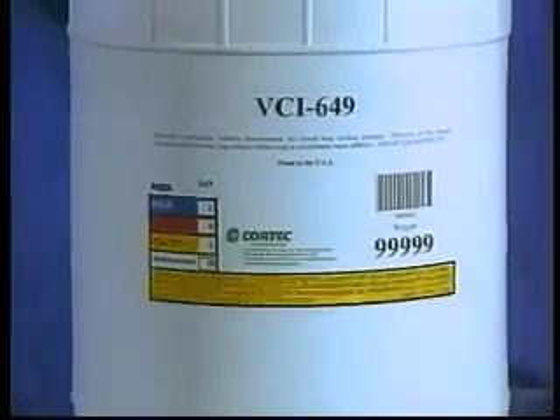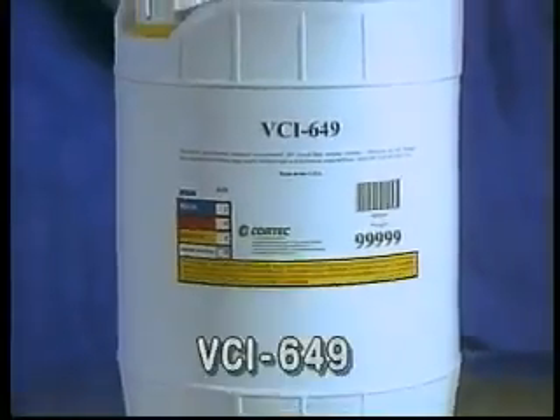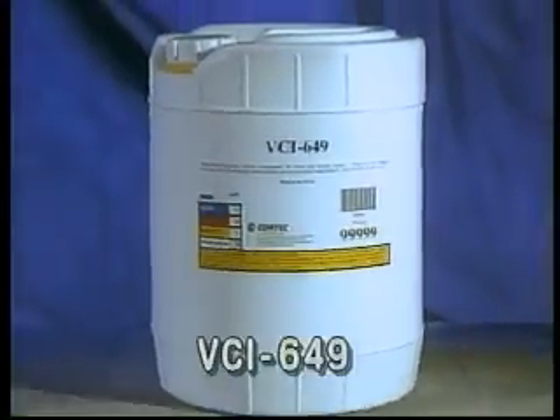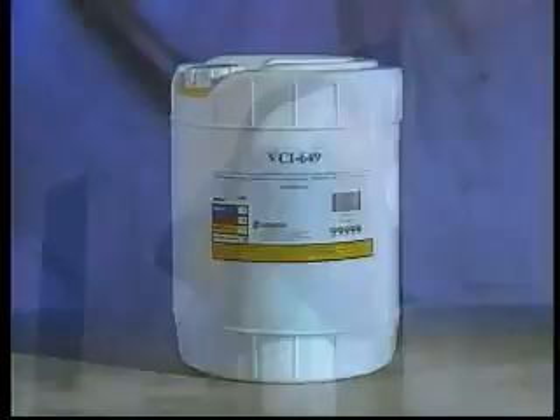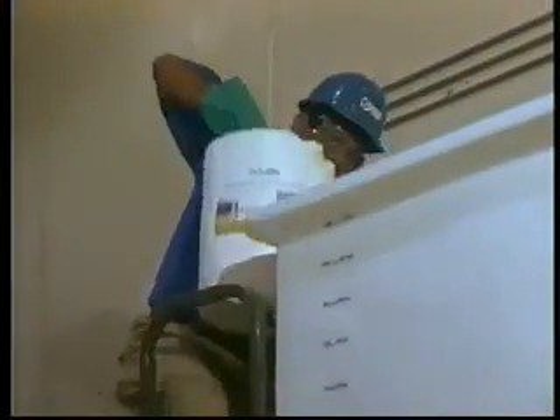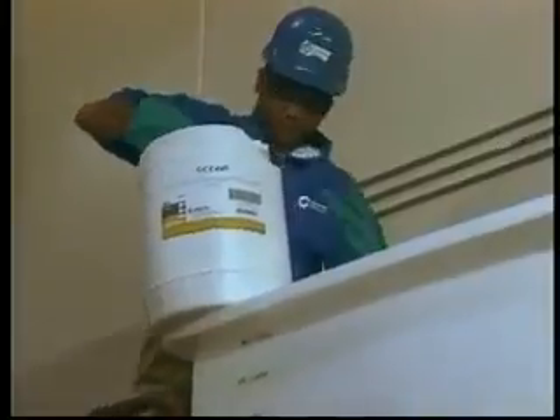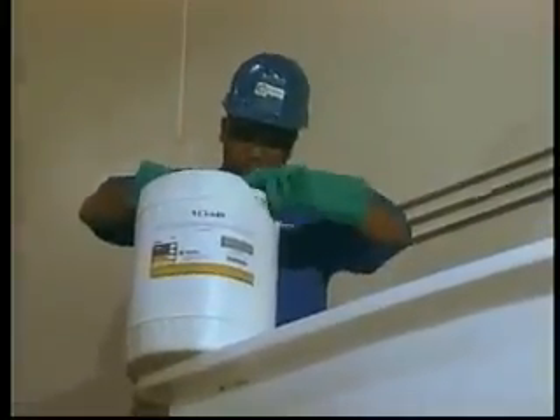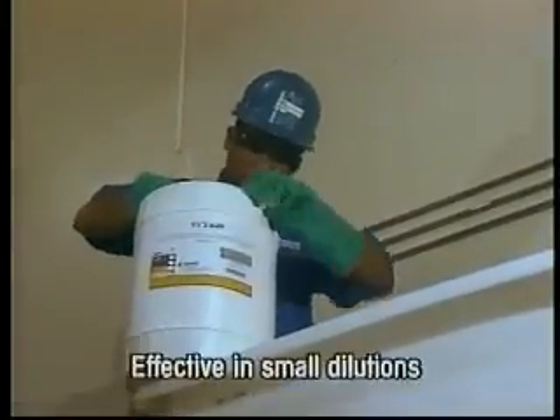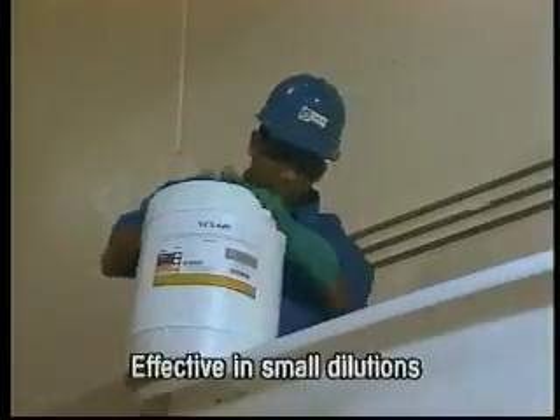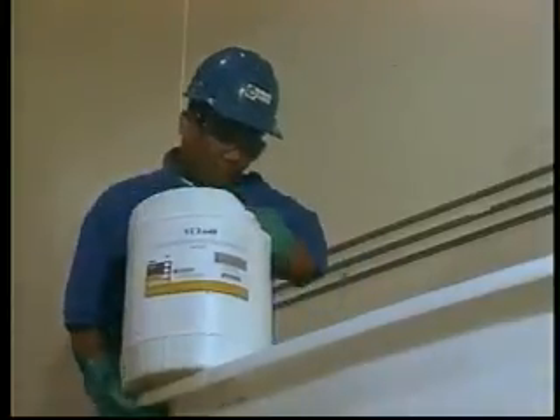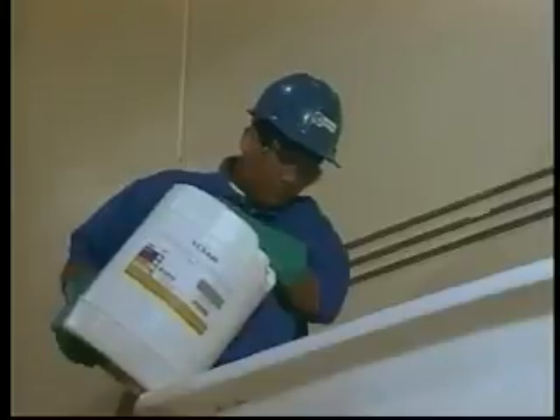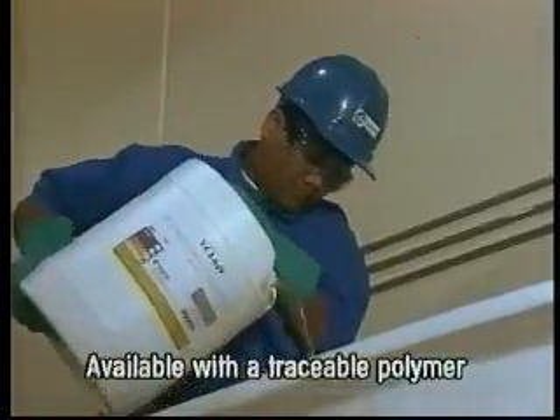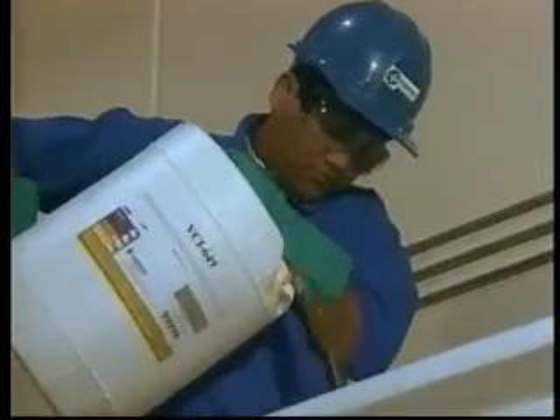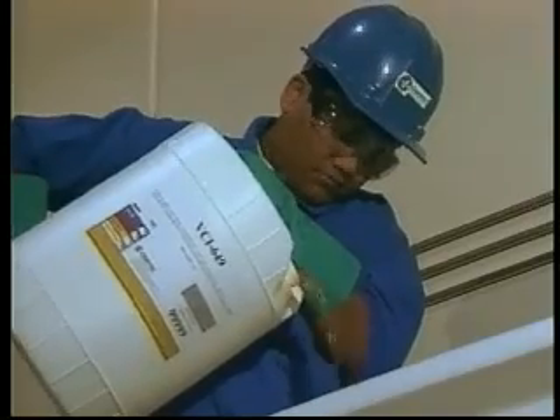Another alternative for layup is Cortec VpCI 649. VpCI 649 is a corrosion-inhibiting liquid that includes all of Cortec's corrosion prevention benefits. Application is easy. Only 0.1% or 1,000 parts per million by volume is needed for effective corrosion protection. VpCI 649 is also available with a traceable polymer and is then known as VpCI 649T.